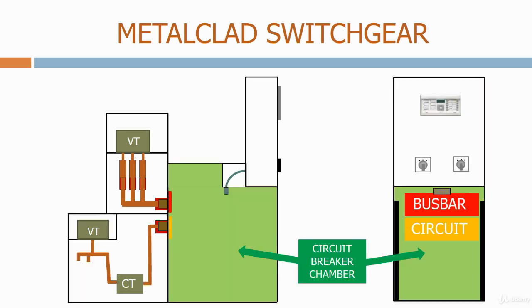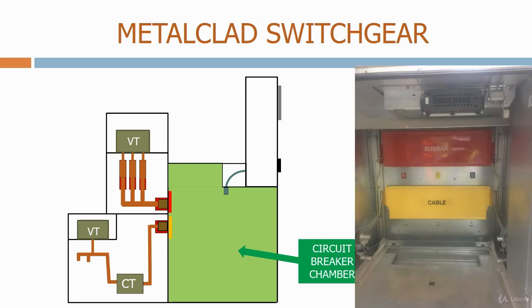Finally, we have the circuit breaker chamber. You will see two shutters, a red one labelled busbar and a yellow one labelled circuit. These shutters are provided to stop anyone accessing the live busbar contacts and live circuit contacts behind them. Here's a typical example of the shutters. When the truck is inserted into the circuit breaker enclosure, these shutters open, allowing the circuit breaker contacts to interface with the busbar and circuit contacts.